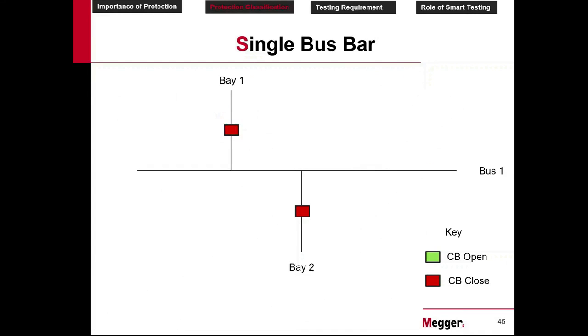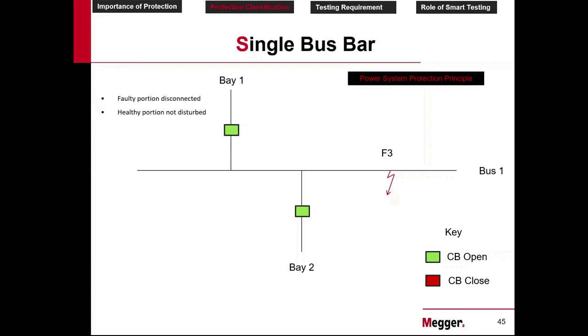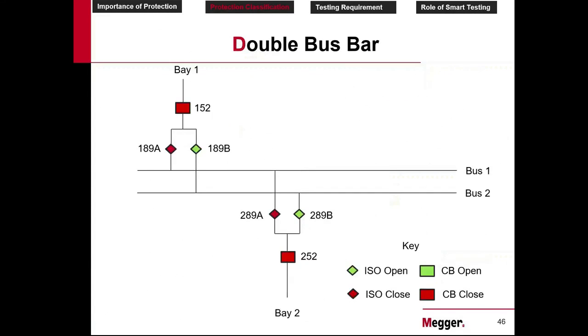So let's see another example. Fault occurs here. Bay 1 is healthy, bus 1 has the fault. Bay 2 is healthy. But which breaker will we trip? The answer is both. And we don't satisfy the principle, because bay 1 and bay 2 are healthy, only bus 1 is faulty. Hence, we need to go for another arrangement. This is called the double bus bar.